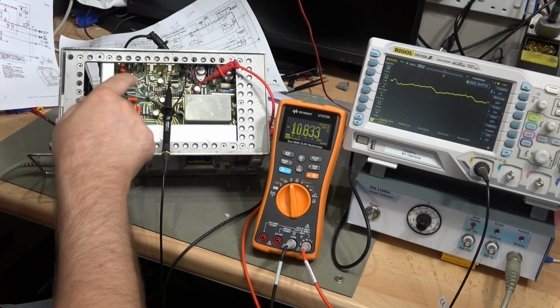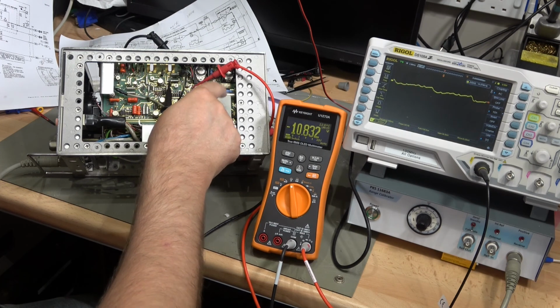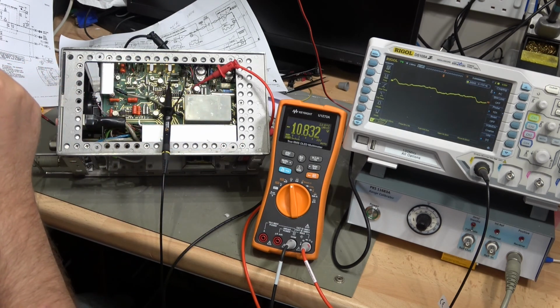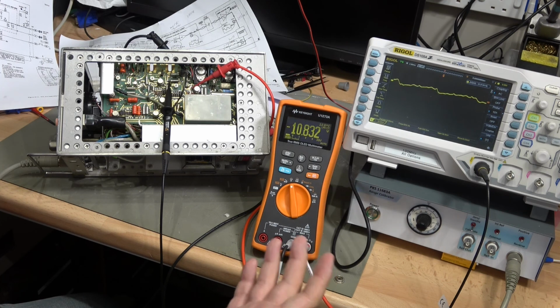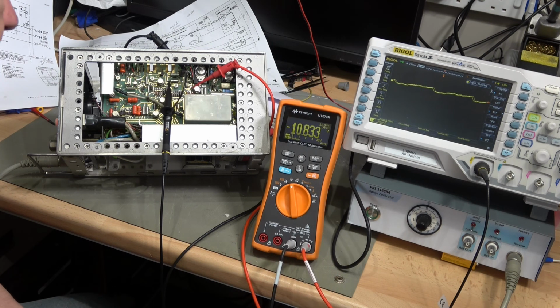Now the reason that it's clipped at minus 10.832 volts is simply because it's a times 7000 amplifier and it's got a volt going into it, so 7000 volts, that's not going to happen. This actually, the test point should mention that you actually need to zero this. You need to have a working sensor on the front in order to get the 0 volts on the front end of this amplifier. And then what should happen is we then get an offset which gives us the voltages we need for the capacitors to create the 0 volt feedback loop with the sensor.